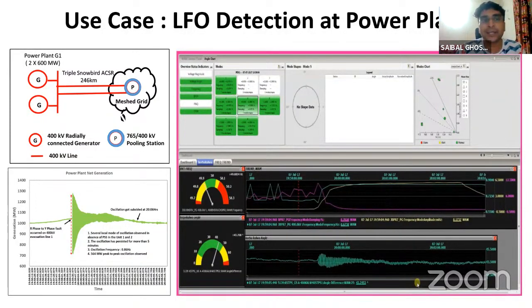Then the operator will try to reduce the load in the inter-area corridor, meaning the tie lines from one region to another. Now how can they do it? They will change the HVDC flow. In India, we have a lot of HVDC across regions, parallel with the AC line. So if we increase or decrease the HVDC, we can change the loading of the AC line, and with this, damping can easily be brought back to the left hand side.